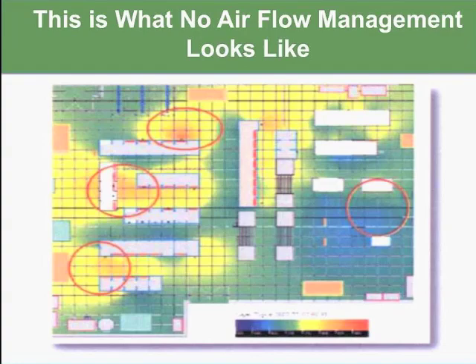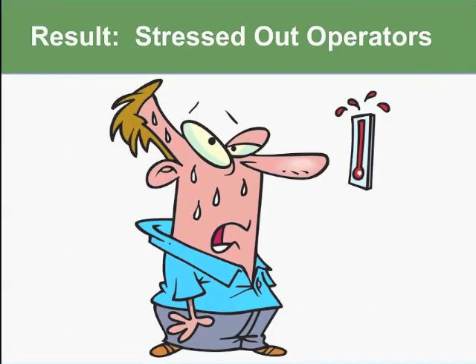If you have airflow management, you might be able to minimize this situation, but again, you don't necessarily have visibility into whether your airflow management is working or not. And as a result, you get stressed out operators because they don't know from moment to moment whether or not their IT equipment is being properly cooled or whether they have an overheating situation, which will then result in some kind of operational failure. And we want to try to avoid that.